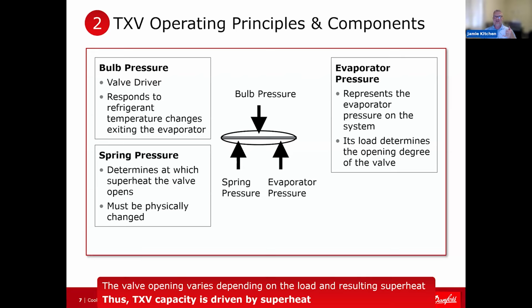It is there to make sure the refrigerant leaving the evaporator is warmer than the temperature it's changing state at. Okay. And that is what we call superheat. So the amount of force that spring puts in, remember, pressure is equivalent to temperature. So if we think of that spring pressure as additional pressure underneath, that's equal to temperature. So if it pushes hard enough to equal 6 degrees or 7 degrees, guess what? That's what we would call static superheat. Some people call it factory superheat. That's the amount of superheat you need for the valve to start opening. That's not what it's going to regulate at. That's what you require to start compressing that spring.